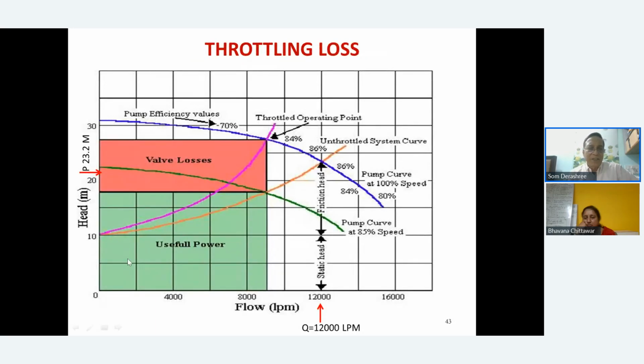This is a typical throttling loss that we have shown here. This is a pump characteristic curve. This is the present PQ in LPM that you wanted, and the head was around 23.2 meters, which was your requirement. But now you need less flow. Let's say you need only 9,000 flow. So you have throttled the valve, but by throttling you have increased the static pressure also. So it has come somewhere around here, and this will result in losses.